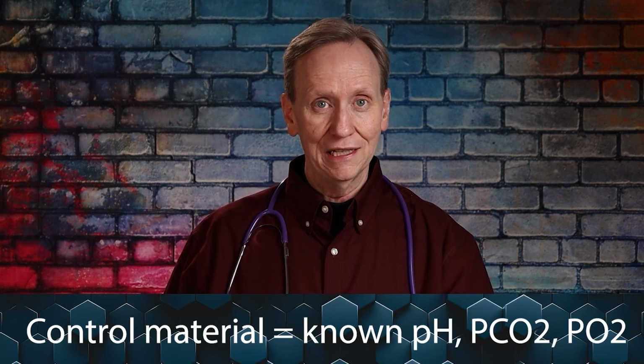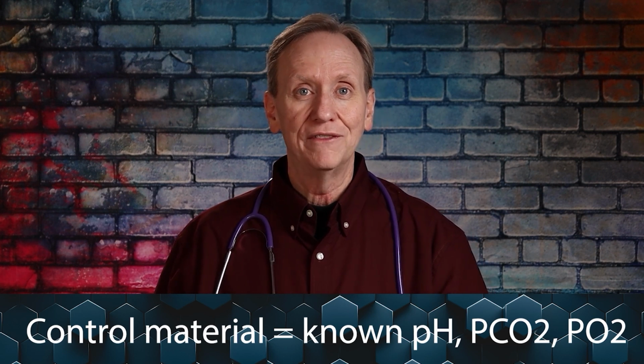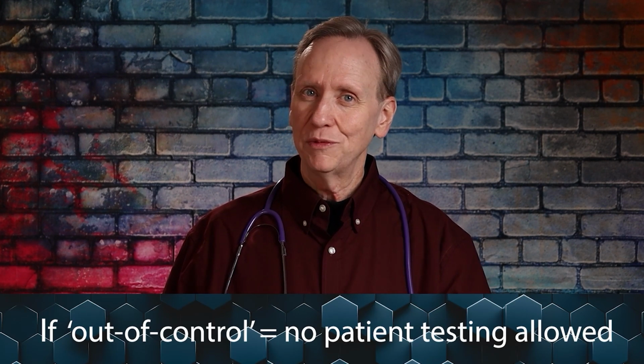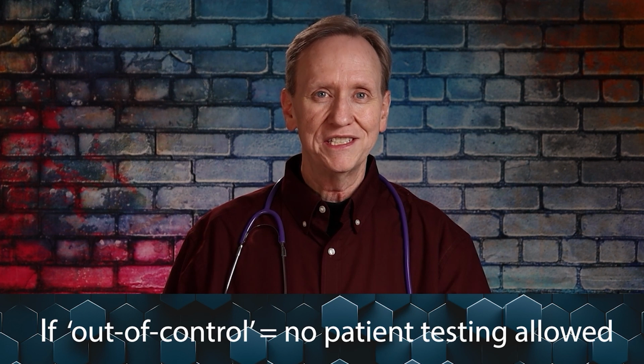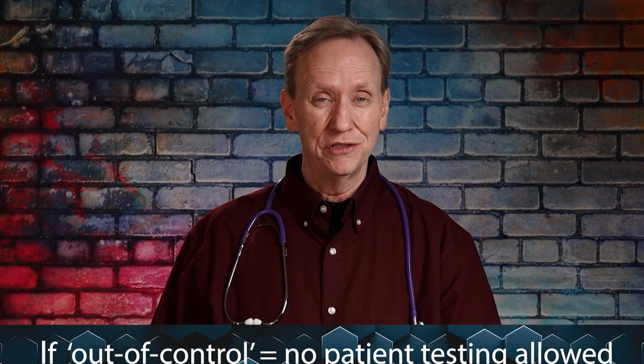When we analyze that material, if the data from the blood gas machine isn't within the range the manufacturer specifies, then the machine is out of control. That means we shouldn't use it for patient testing or reporting, and certainly shouldn't act on its results to change patient care.